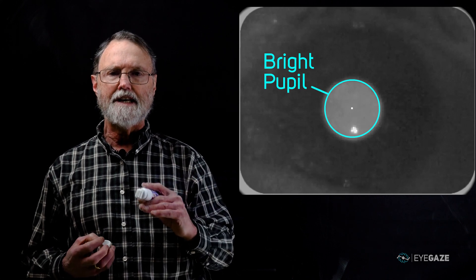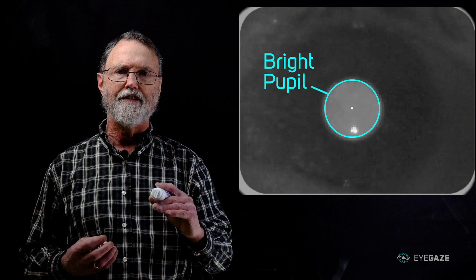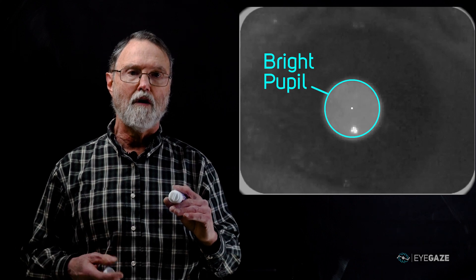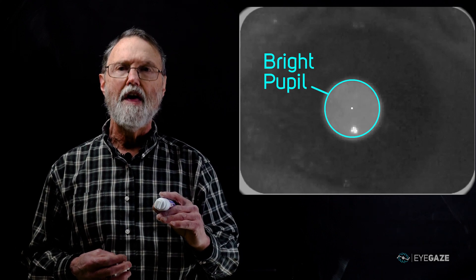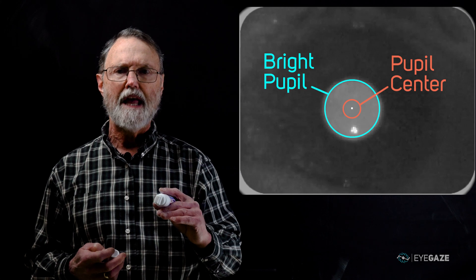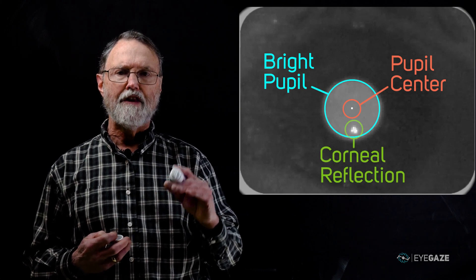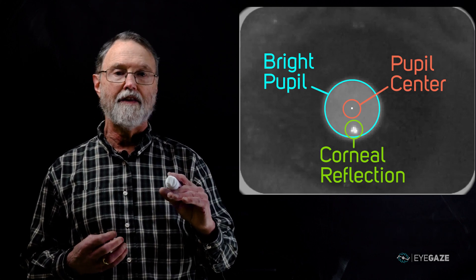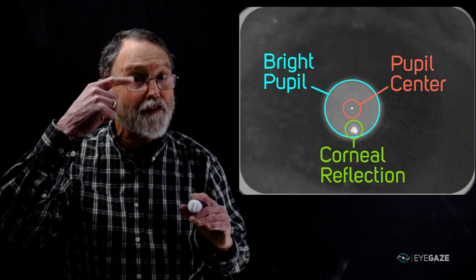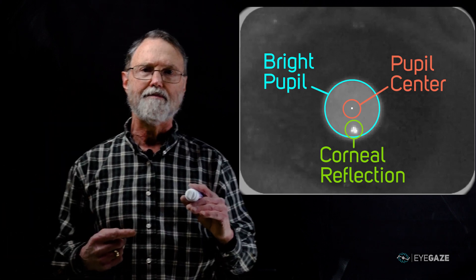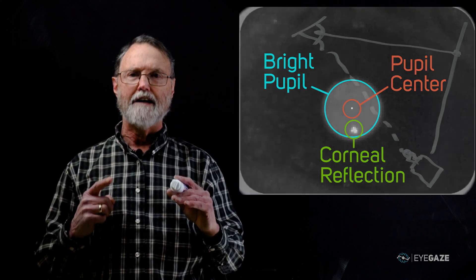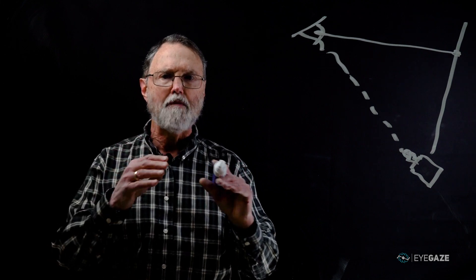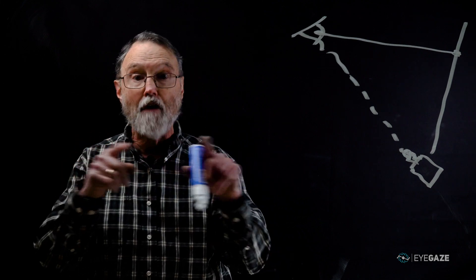This happens because the LED is mounted at the center of the camera lens. To measure where the eye is looking, there are two critical locations in the eye image. The first is the pupil center, and the second is this really bright spot called the corneal reflection. This is the reflection of the LED light off the corneal surface of your eye. And here's the key to eye tracking: as your eyeball rotates around, the relative positions of your pupil and corneal reflection move around with it.